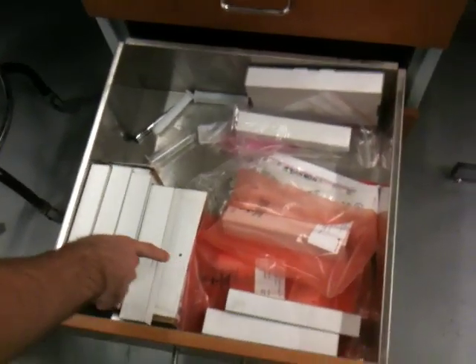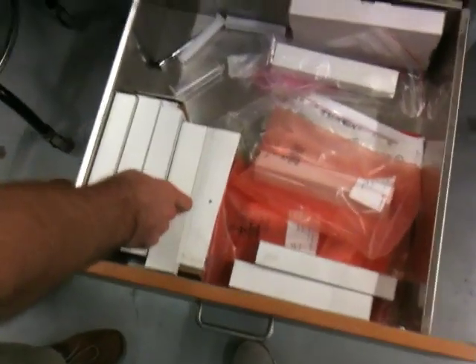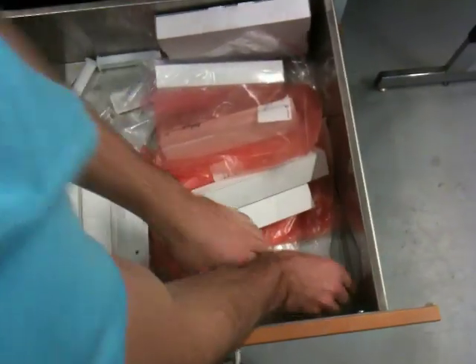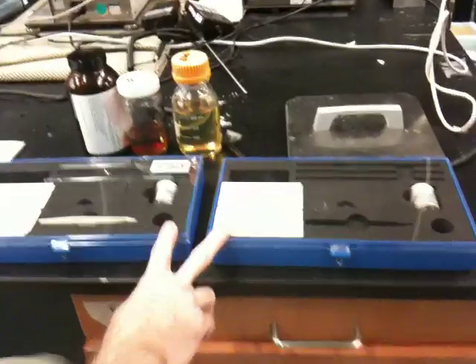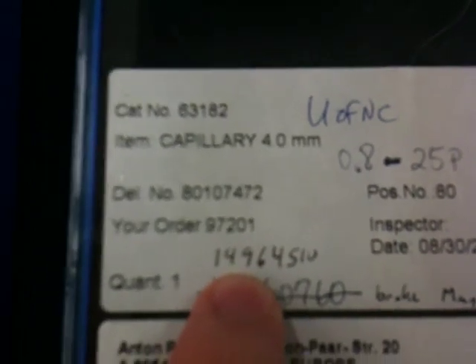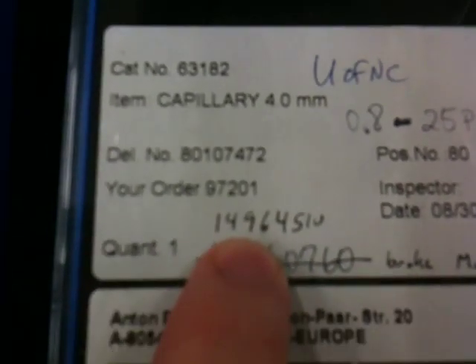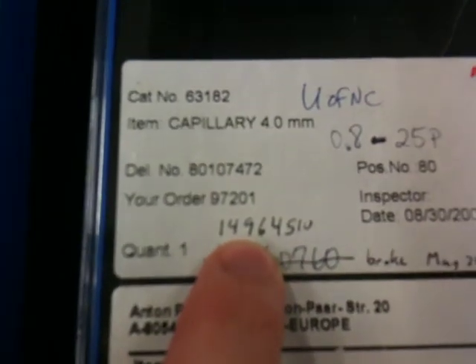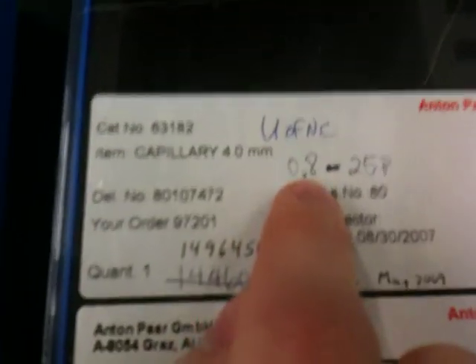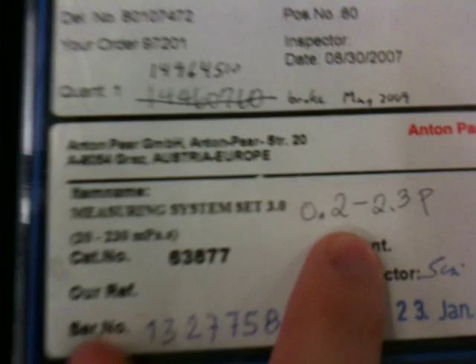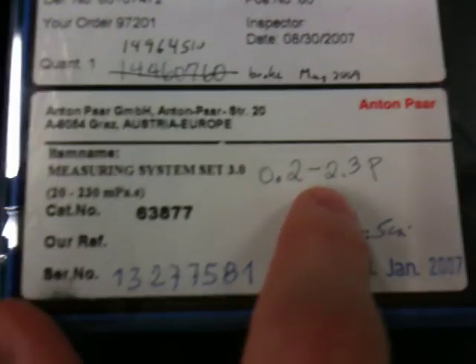Okay, down here, these are extra capillaries in here. There should be. And usually they'll stay in these two containers. And if you look on here, you'll find this number was the one that matched up to the capillary we're using and the calibration that you had to choose on the computer. This is the one we're using, and it has this range. Now this is in units of poise. The machine gives it in units of centipoise, I think. So for this capillary, it has this range. This capillary, it's a little bit smaller, has this range.